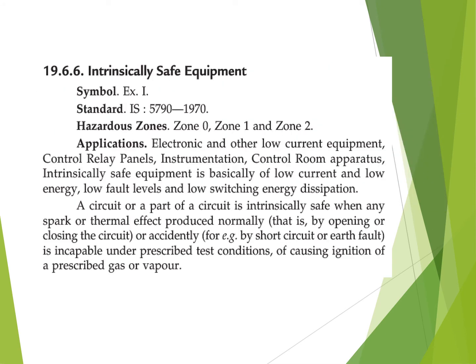Intrinsically safe equipment comes under type I, and it can be used for zone 0, zone 1 and zone 2. This is very important. Electronic and other low current equipment, especially relay panels, instrumentation, and control apparatus, are all intrinsically safe equipment. Basically, they are low current and low energy equipment. A part of a circuit is intrinsically safe when any spark or thermal effect produced normally or accidentally is incapable, under prescribed test conditions, of causing ignition of a prescribed gas or vapor.